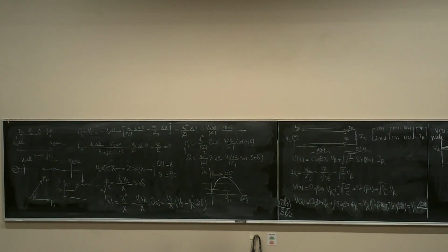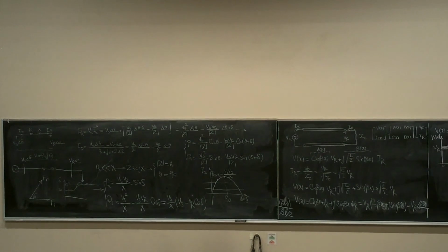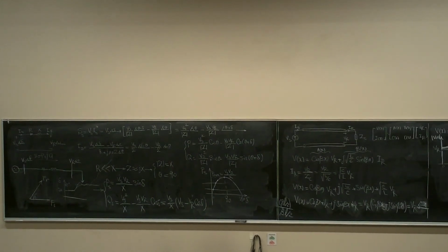But as soon as you have more load, the frequency in the power plant is going to drop. But what is important is the frequency at the load. You know, how much is the load? We want to keep it at 60 hertz, plus or minus maybe 0.01 or 0.02. But in the power plant, it's going to change more. We are not worried about that. Maybe it changes by like 0.2 hertz, something like that. But they call it droop control.